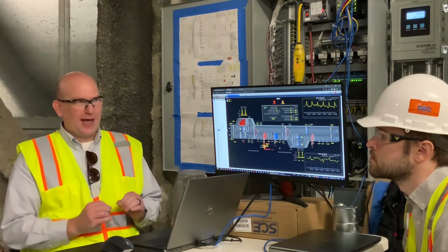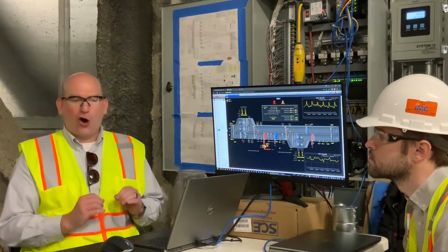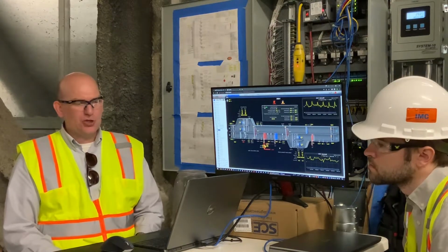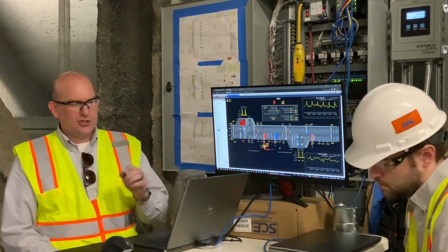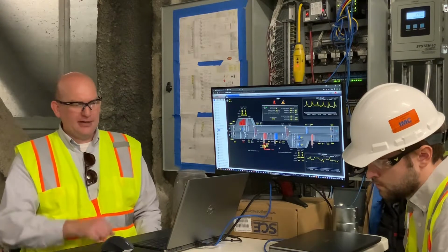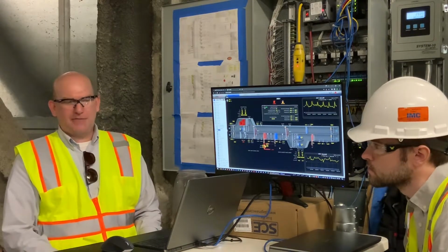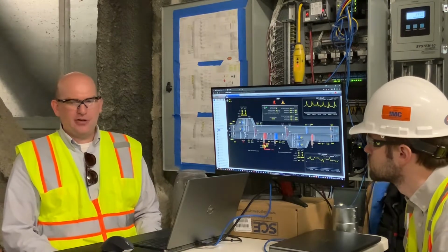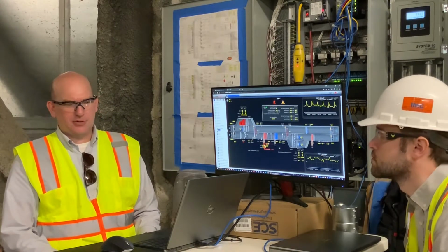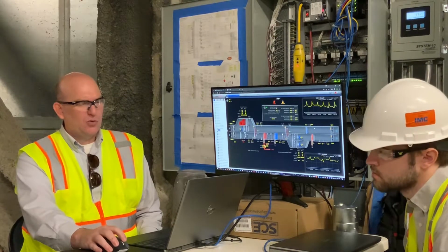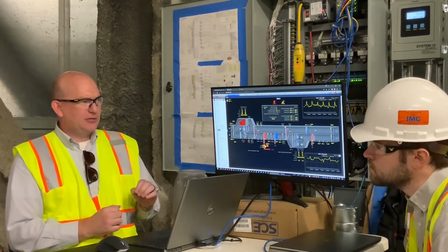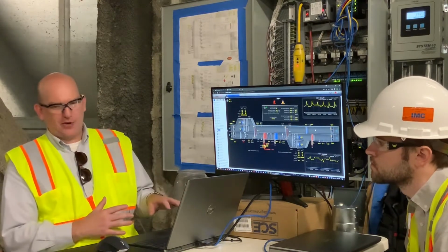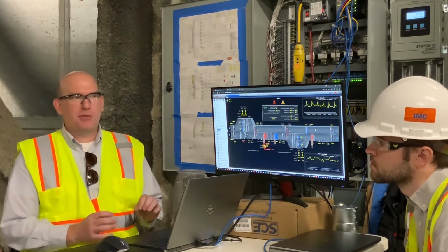So all of that type of functionality is hardwired to the VFD. So what that means is that if for some reason you wanted to turn a fan on by hand, if you go and turn the fan on by hand, that VFD is going to open those dampers. Okay? If the VFD faults out and shuts down, the VFD is going to shut those dampers. Okay? So the potential for a problem of backwards flowing air through a unit has been minimized as much as possible.